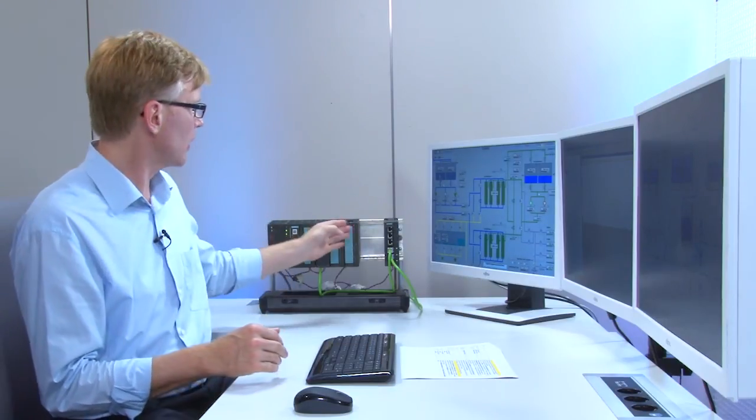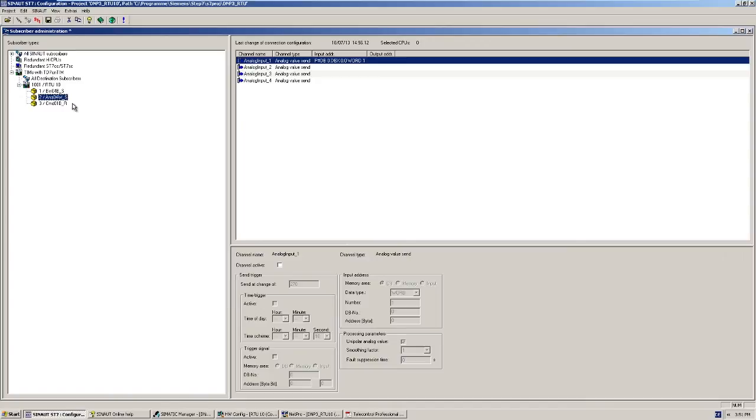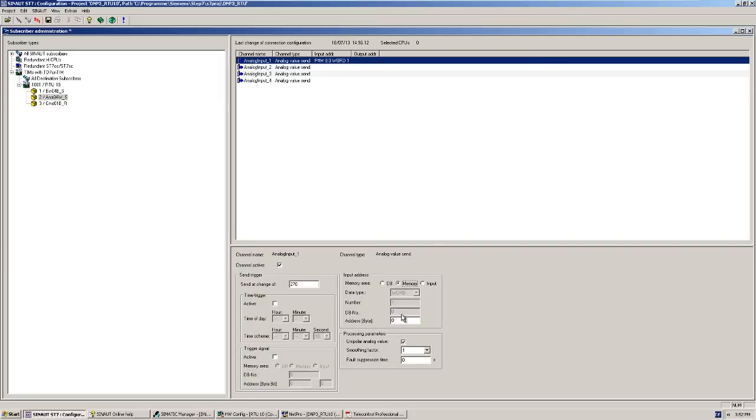Next, I set the parameters of the data object for transmitting the analog value. The analog value is read directly from the analog input module and converted to a physical measured value of type integer in the CPU. For the analog value, the first channel must also be activated and we specify the address where the CPU has stored the converted analog value.